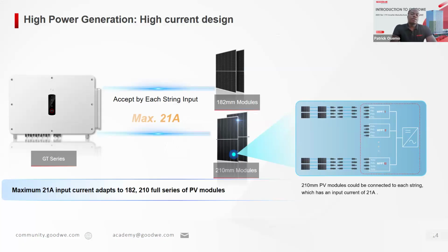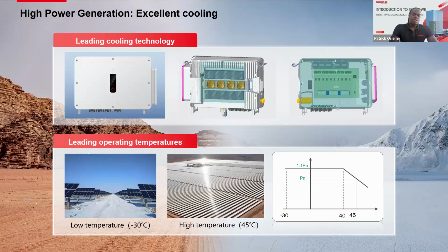I mentioned the high power input current of the MPPT. You can see lately the panel sizes are increasing. We have the 182 millimeter wafer sized panels. We have the 210 millimeter wafer sized panels. Now, these are the high power panels between 550 watts to 650 watts, 700 watts, those kind of panels. These panels are compatible with the GT series without clipping. So you can either do one string per MPPT or even two strings per MPPT, and you don't experience clipping from the DC side of the inverter. And given that our product is IP66, the GT series is IP66, then you have the capability of installing the inverter outdoor. Even if you're installing the inverter outdoor, the inverter itself has a very efficient cooling technology.